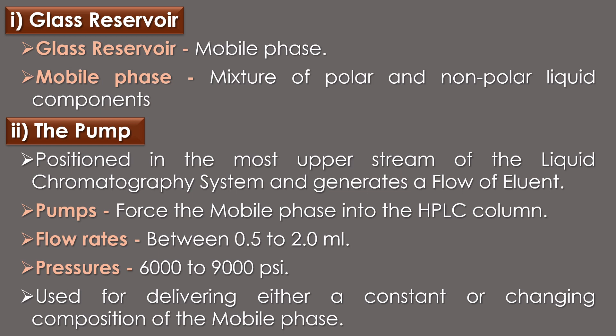The pump is positioned at the most upstream part of the liquid chromatography system and generates a flow of eluent from the solvent reservoir into the system. The role of the pump is to force the mobile phase into the HPLC column at desired flow rates, expressed as mL per minute. Flow rates between 0.5 to 2 mL/min are usually sufficient for most experiments. Pumps in modern instruments can reach pressures in a range of 6000 to 9000 psi. Pumps can be used for delivering either a constant (isocratic) or changing (gradient) composition of the mobile phase.